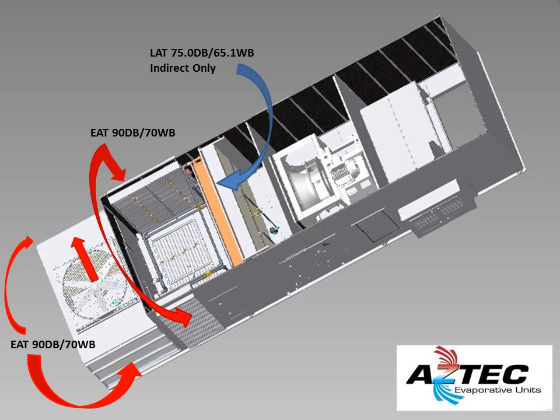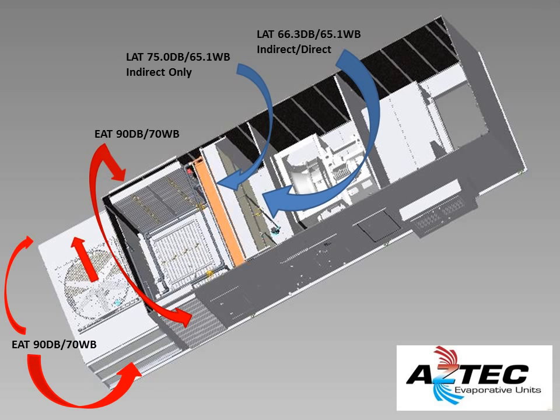With an entering air temperature of 90-degree dry bulb and 70-degree wet bulb, you will see after the indirect coil a leaving temperature of 75-degree dry bulb and 65.1-degree wet bulb. This is a 15-degree drop in the dry bulb temperature, and this is without any mechanical cooling. After passing through both the indirect and the direct section, you will see a leaving air temperature of 66.3-degree dry bulb and a 65.1-degree wet bulb. This is a 23.7-degree drop in the dry bulb temperature, again without any mechanical cooling.